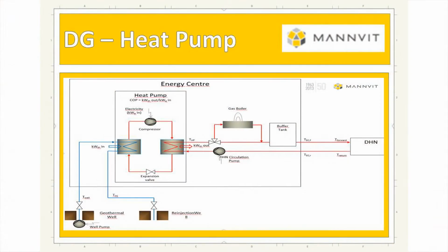Deep geothermal with heat pump augmentation - this was a system we looked at up in the northeast of the UK. We've got our geothermal wells for abstraction and rejection, with broadly about a 55-degree temperature. Now, 55 degrees for district heating purposes - yes, on very modern housing estates where everything's got underfloor heating, you could probably get away with it, but in a retrofit example it's never really going to happen.